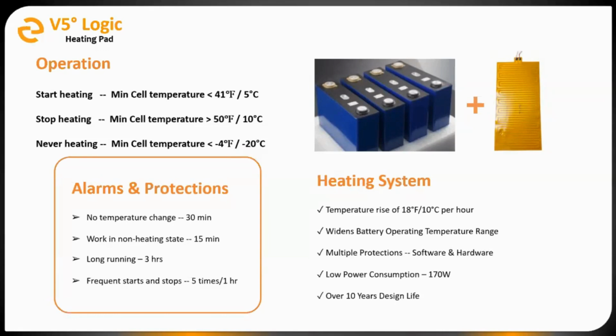I mentioned we do have some protections on this internal component in the battery. So basically the BMS is looking at the battery cell temperatures and how the heating pad is running, or if it's not running. And depending on what's happening at that moment, it may give an alarm. So one of those protections is if the heating pad goes on, it's activated, and the battery doesn't detect a temperature change within 30 minutes. So in other words, the heating pad is on and the battery thinks it's heating, but the temperature is not actually increasing. So that's going to indicate that there's a problem to the BMS, and it will give you an alarm and turn off for protection.